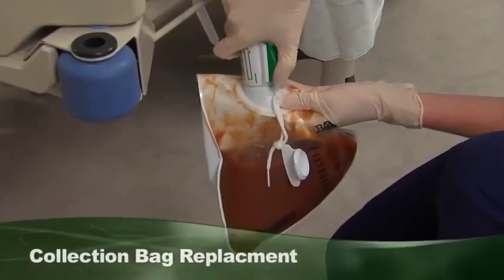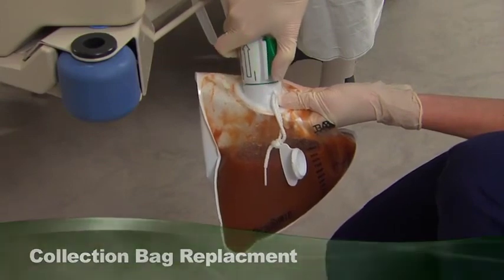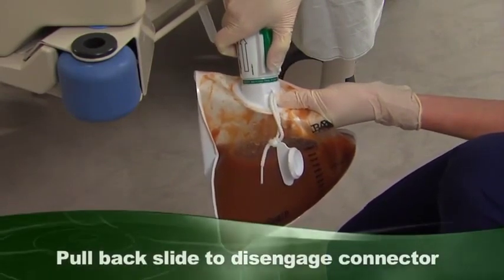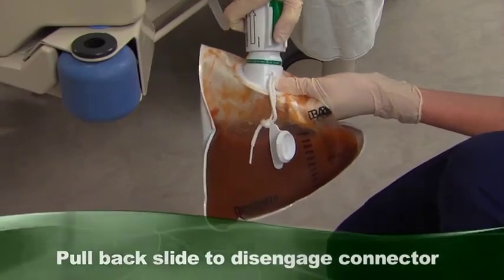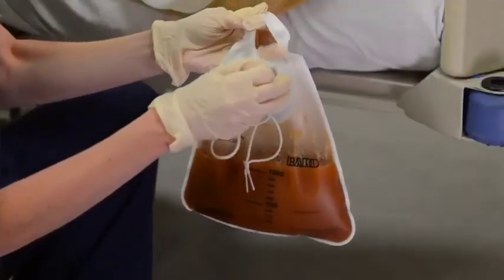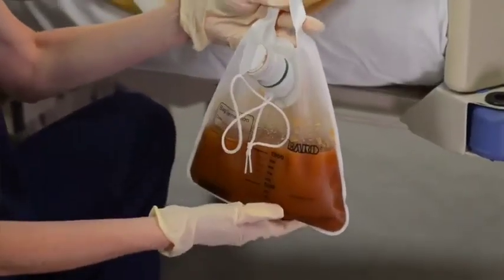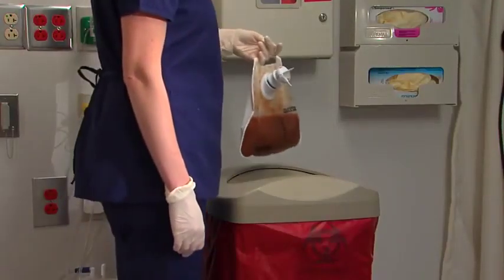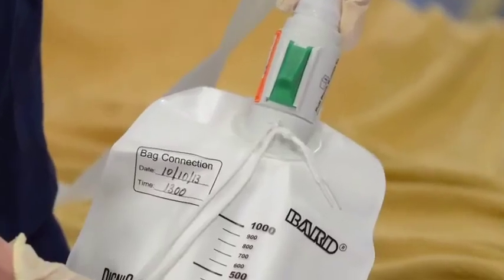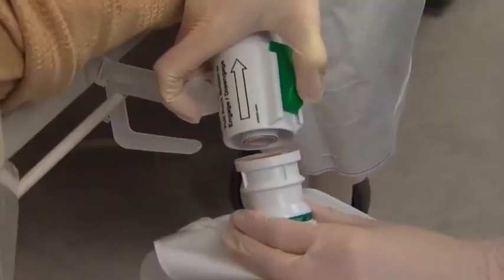To remove the collection bag, grab the piston valve connector and gently pull backward on the switch located on the slide of the connector until the piston ejects from the collection bag hub. The piston valve and bag hub should close off automatically in this process to minimize inadvertent exposure to feces. Once the bag is removed, insert the bag cap into the hub connector and dispose of the collection bag in accordance with institutional protocol for disposal of medical waste. Closing the bag not only minimizes spillage, but also reduces contact with potentially infectious microorganisms. If possible, remove the bag from the patient room to eliminate odor. Date the new collection bag and replace it by securely snapping a new bag to the connector.